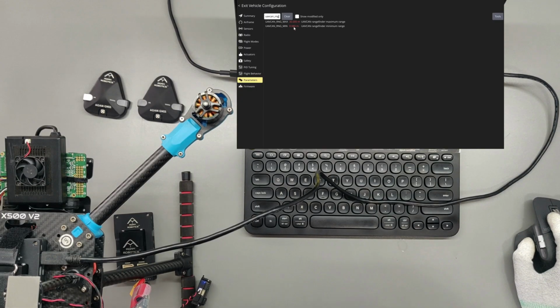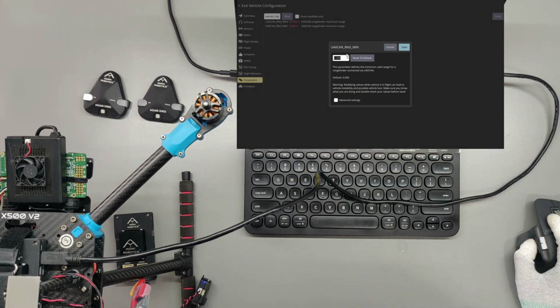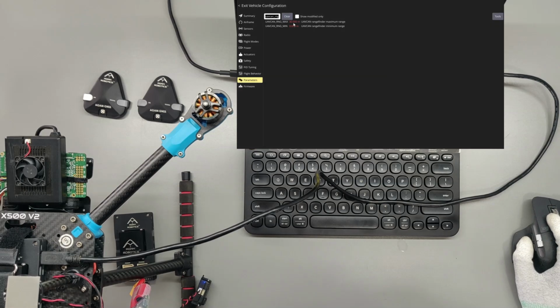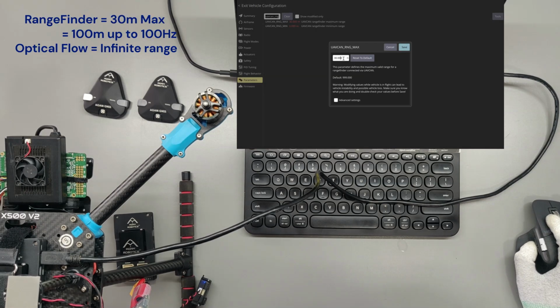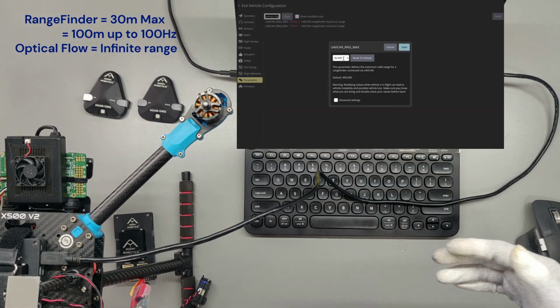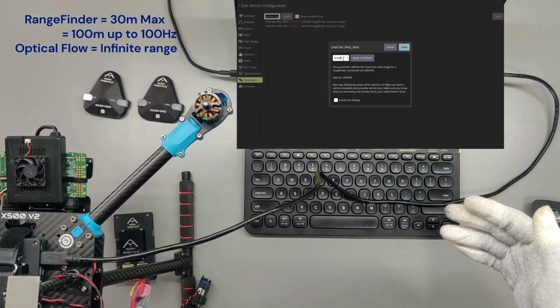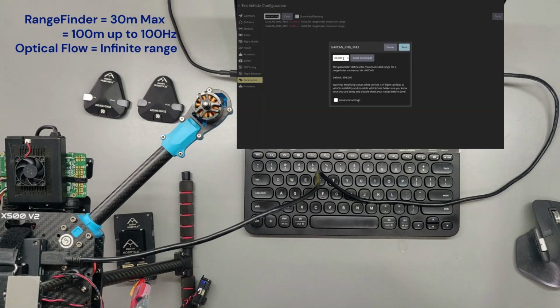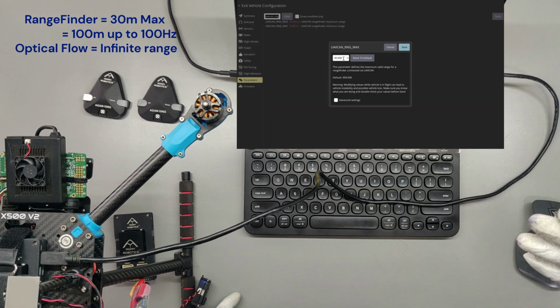If it is not set to any value, or it is slightly higher, the default is 0. So you need to set this to 0.08 m, which is the minimum distance the rangefinder can measure. And the max value, set it to 30 meters if it is not. Based on your environment, you can start increasing this value and test it up to 50, 60, 80 meters. The sensor itself can do up to 100 meters.